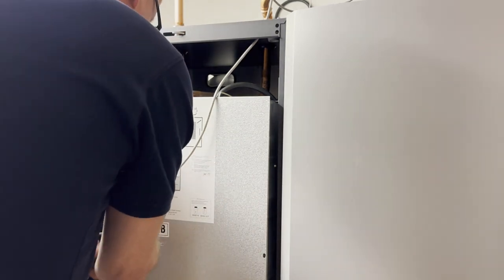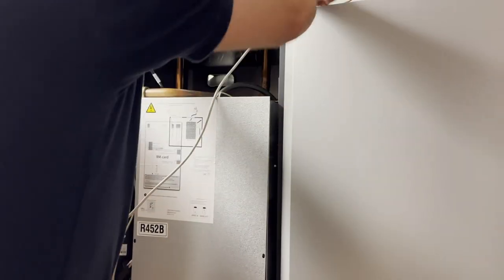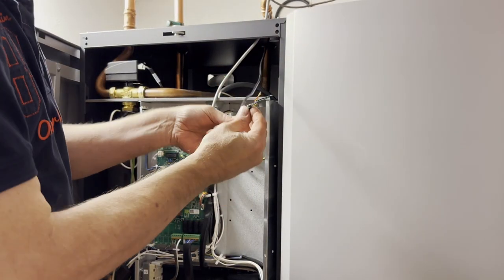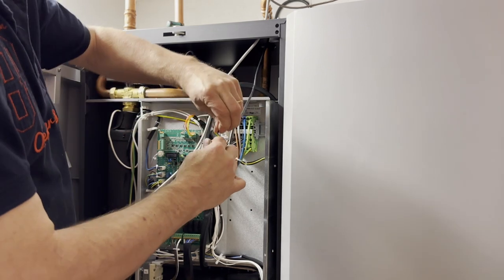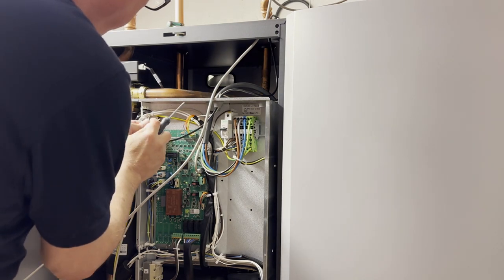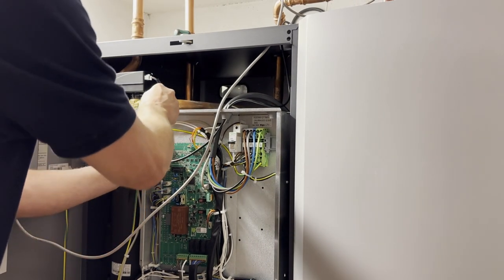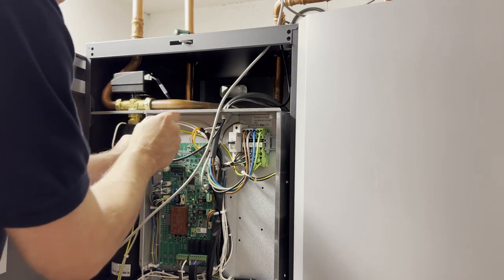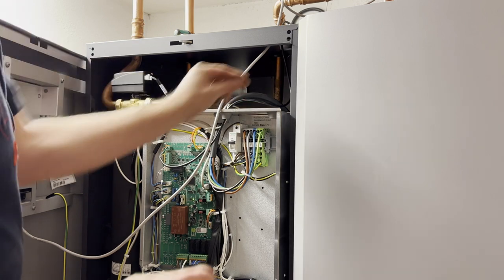For the indoor sensor we need to open it up, and to be on the safe side you should turn this off. Here's my two-wire for the temperature sensor — it's a PT-1000 sensor resistor, so it doesn't matter which way you connect the cables. There, let's close this up. Connected.